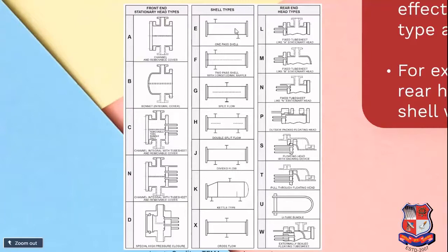Okay. Now, in shell types, you can see E stands for one shell pass, F stands for two shell passes. Here, again, I would like to show you a longitudinal baffle where it splits the shell side fluid in two parts. Whereas G gives a split flow. In between, there is again a longitudinal baffle, but at a different arrangement. H gives double split flow, J has divided flow, where one stream is inlet and two streams are outlet from the shell side. K is a Kettle type of heat exchanger. Basically, those are boilers. X is a cross flow. Cross flow stands for a perpendicular flow direction with the tube side flow. Now we will understand this with an example.